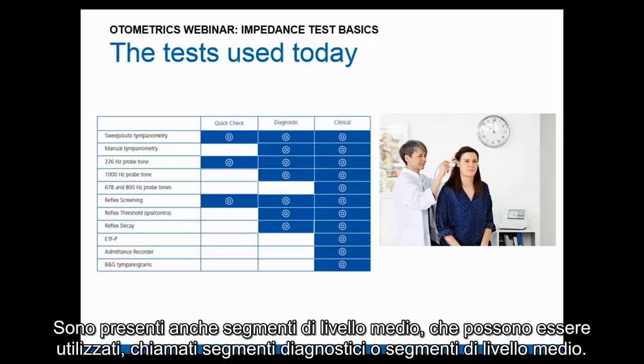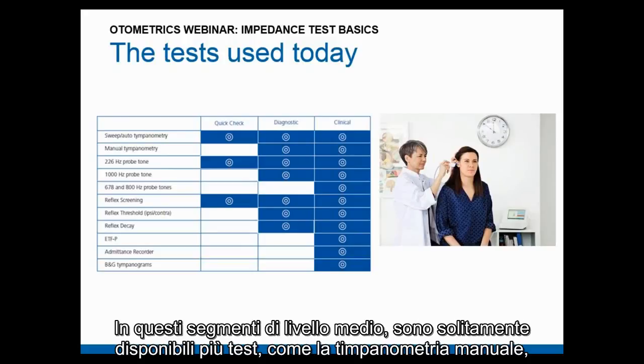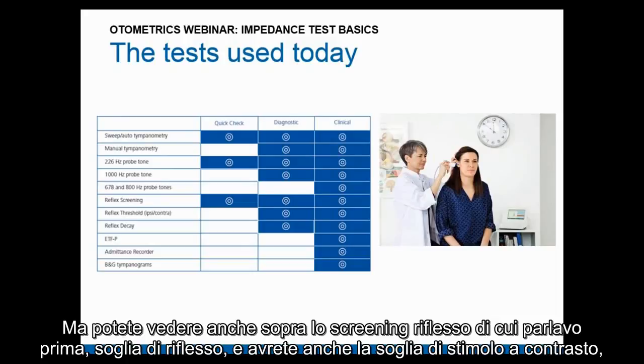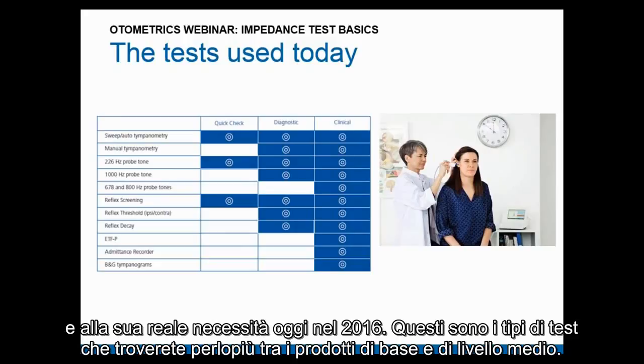The mid-range segment, also called the diagnostic or mid-segment, includes more tests like manual tympanometry, which allows the user to adjust pressure manually with a wheel. You also find reflex threshold on top of reflex screening, contralateral stimulation threshold, and reflex decay — though reflex decay's reliability and relevance in 2016 can be questioned.